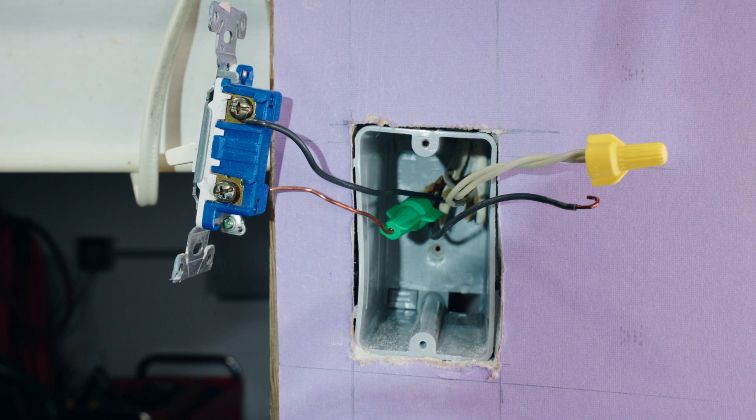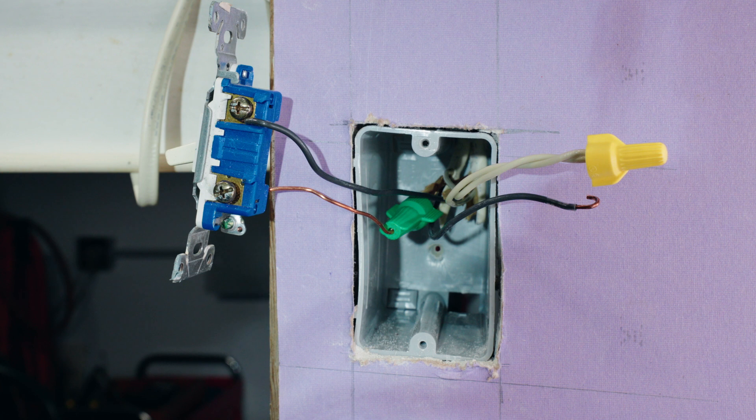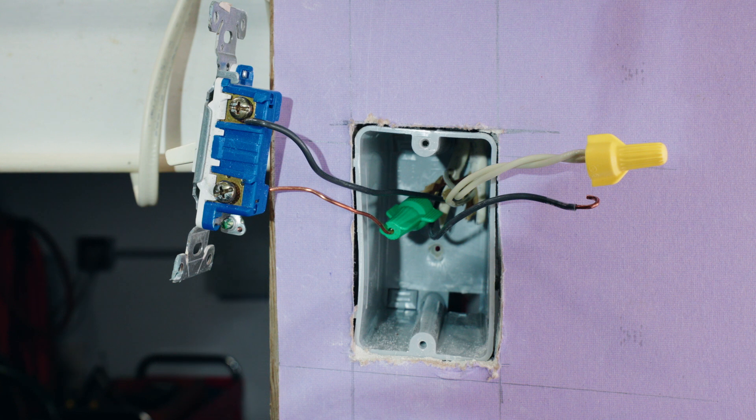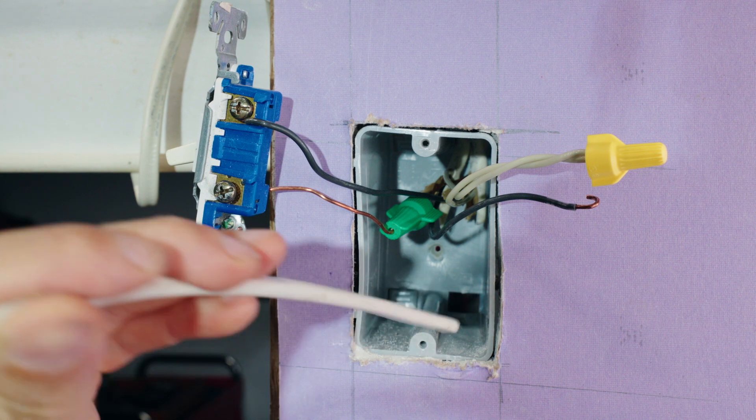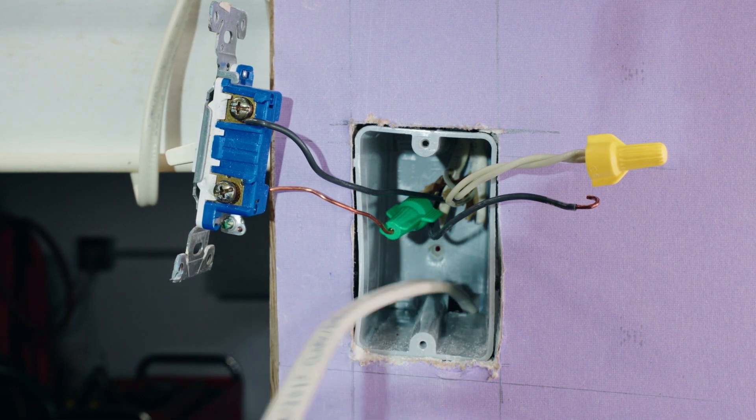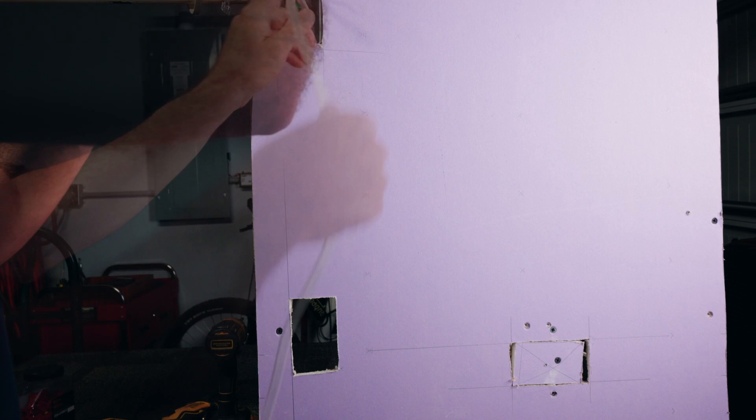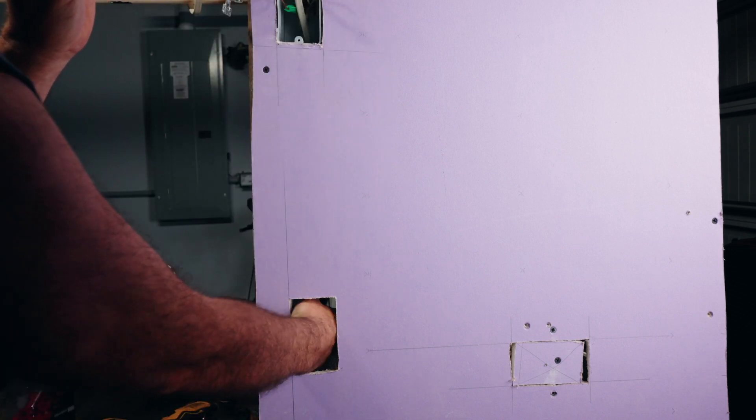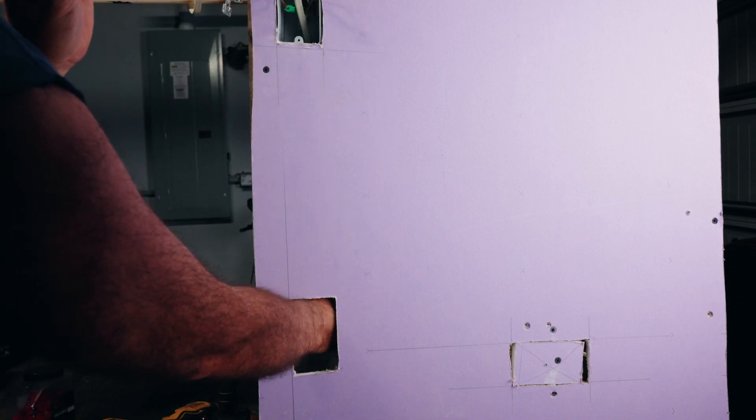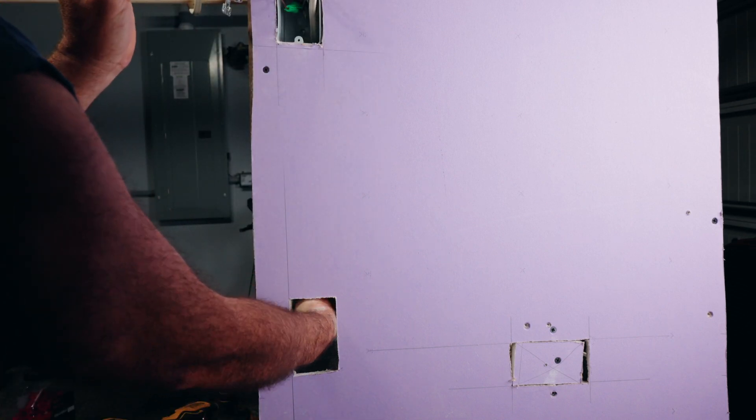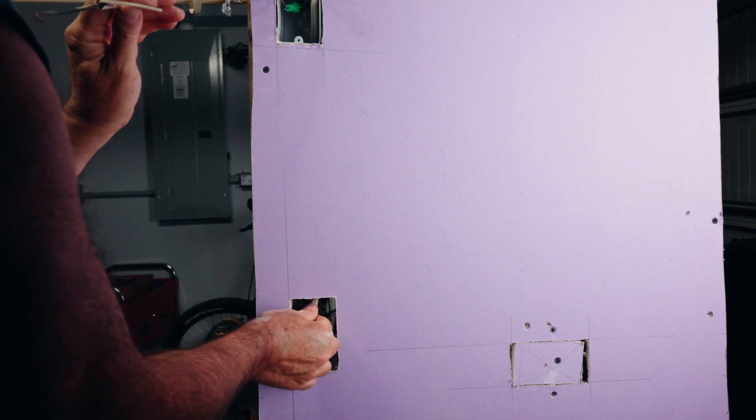Next, you'll want to make sure of what type of wire you have in your box. If you're running on a 15-amp breaker, then you should have 14-gauge wire. If you're on a 20-amp breaker, you should have 12-gauge wire, and you want to make sure to put 12-gauge wire back to your new plug. We're using 14-gauge wire. Just feed it down. Sometimes you'll have to put your hand in the hole and search around in there.